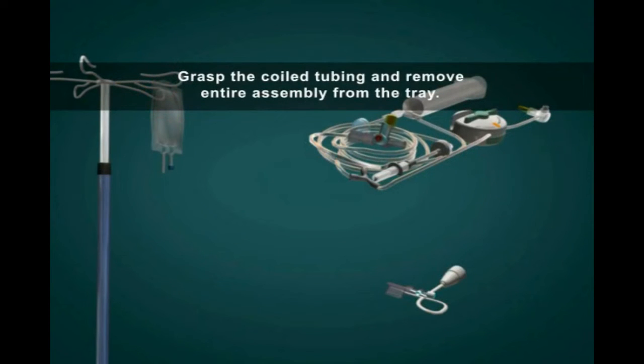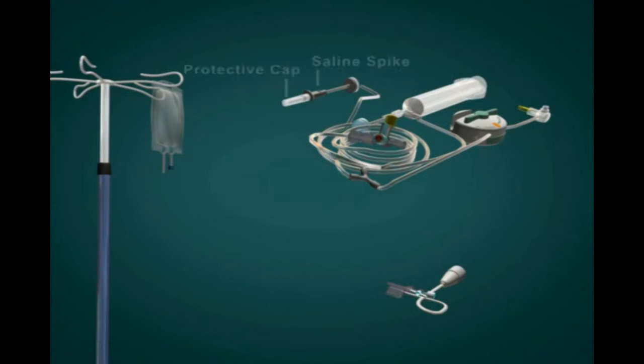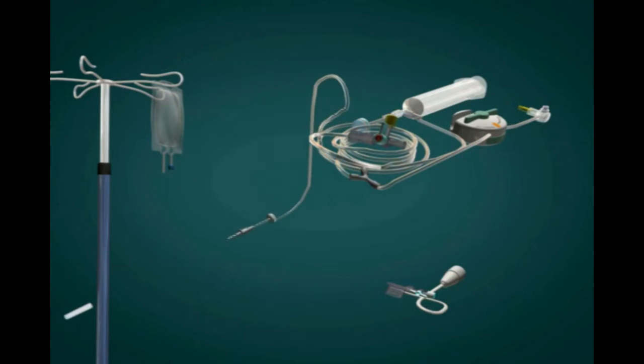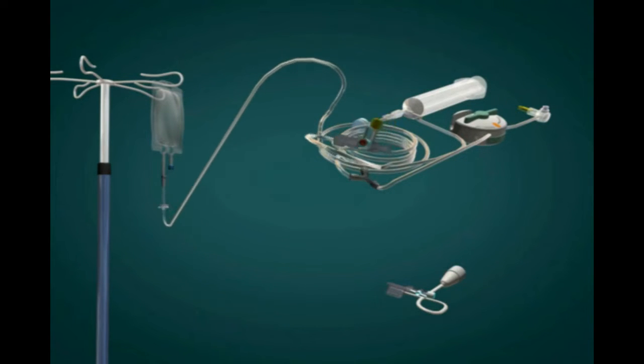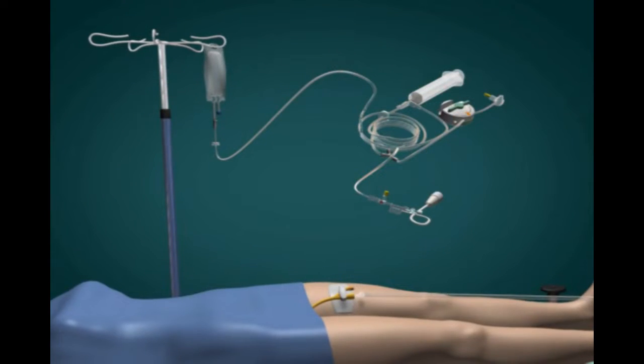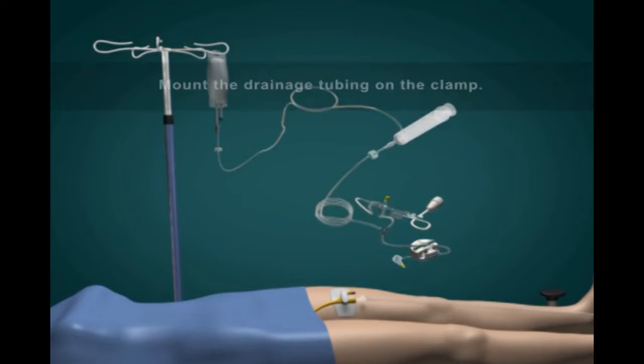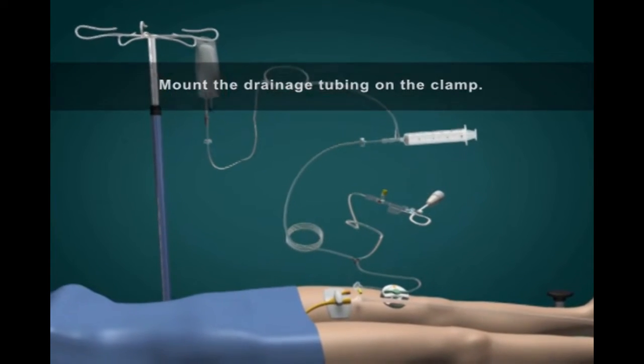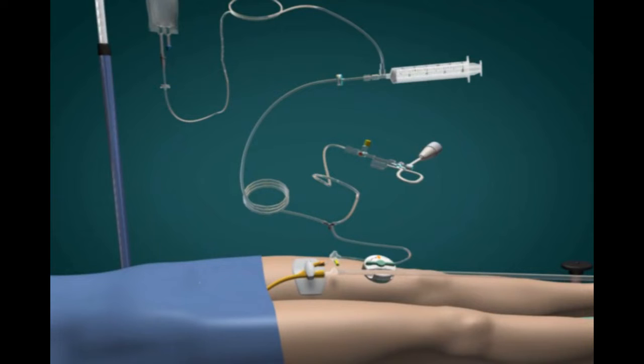Grasp the coiled tubing and remove the entire assembly from the tray and verify all tubing connections are secure. Remove the protective cap from the saline spike and insert the spike into the saline bag. Connect the transducer to the end of the tubing labeled transducer using the provided stopcock as needed, depending on the transducer assembly available. Mount the drainage tubing on the clamp. Decide whether the pressure transducer will be mounted on the pole or the patient.